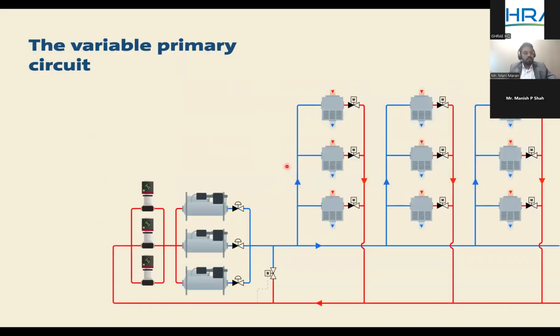Let's get into a little more detail. Let's start with the variable primary system, which is the most efficient system that we have in today's design. This is a pretty energy-optimized design compared to primary-secondary or fixed primary with variable secondary. But let's see what we need to adapt in terms of designing variable primary with distributed pumping, how the control philosophy will change, what design changes we need to make, and what saving we can expect in terms of percentage. Let's get into the detail of the design.